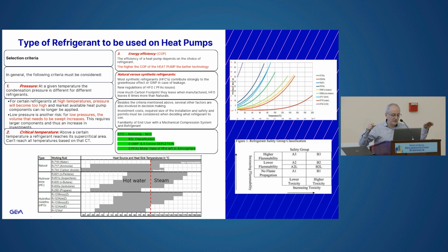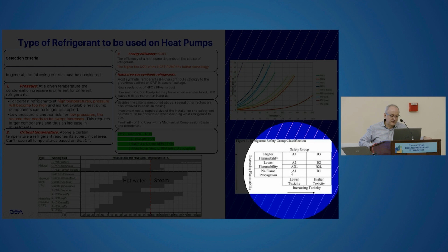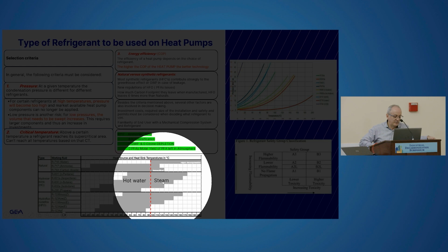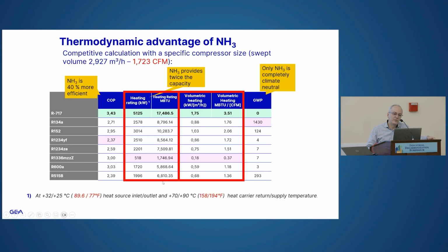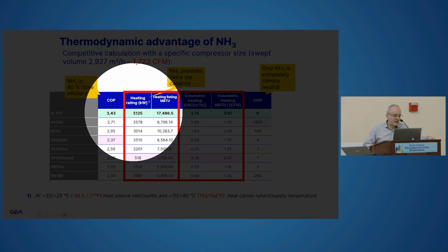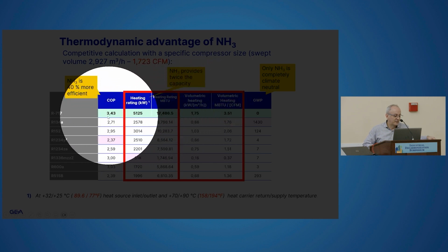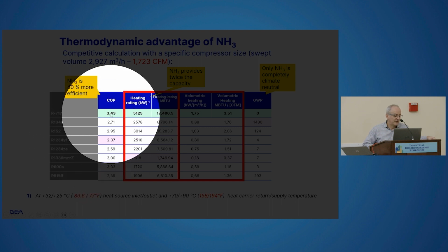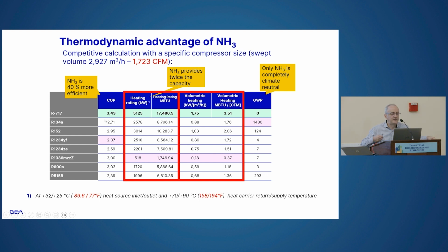But also now you're falling into a lot of these ASHRAE classifications, that's A1 or B2L or A3, depending on toxicity and flammability, and also if you're running into high temperatures like making hot water or making steam temperatures. So what happens, we're using ammonia because we're still finding that ammonia is one of the best refrigerants so far. Ammonia has one of the highest heat pump capacities, what we call volumetric heating capacity. This is a comparison between ammonia and synthetic freons or HFOs, where you can see the COP of ammonia is always the highest. Unfortunately, ammonia is toxic, so you have to have some management around ammonia.